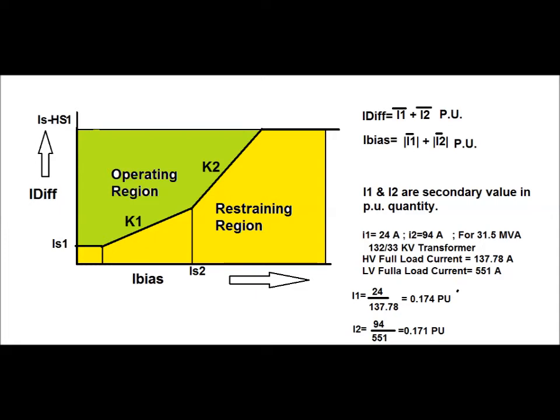For the red phase, I1 equals 24 amperes (HV side primary current) and I2 equals 94 amperes (LV side primary current). The transformer rating is 31.5 MVA. For the 132 kV HV side, full load current is 137.78 amperes, and the LV side full load current is 551 amperes. Therefore, I1 in per unit equals 24 divided by 137.78, which comes to 0.174 per unit. I2 in per unit equals 94 divided by 551, which comes to 0.171 per unit.